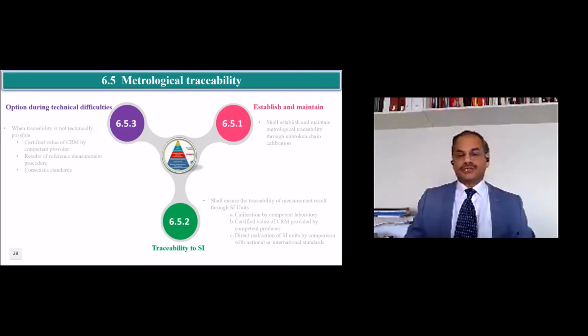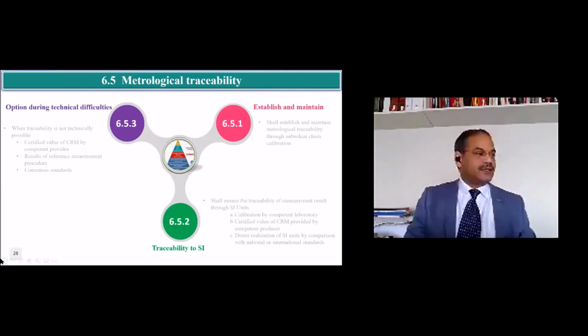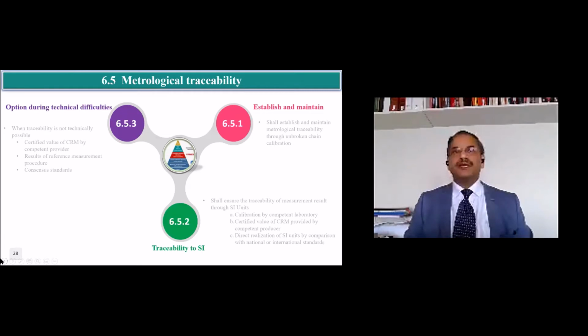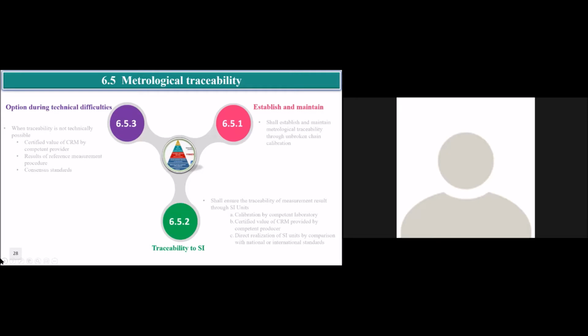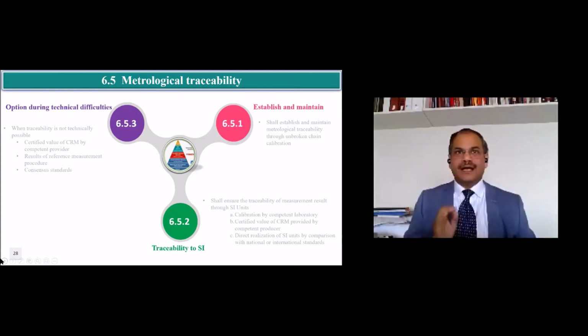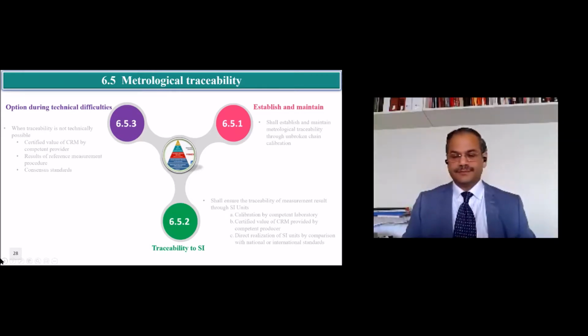Now, come back to Suresh Babu's question. Suresh Babu says he has some criticism from the assessment body that you are asking the manufacturers to do your calibration. Yes, he can do your calibration, there is no question at all, as long as he can produce a traceability certificate which is traceable to the SI unit. No question at all. Am I clear, Suresh Babu? Yes, sir. Did he provide any traceability certificate, or is he just saying this baby is good? He is providing traceability. And traceability to what? Traceability to his company standards, which they maintain. Not acceptable. It has to be traceable to the SI unit.